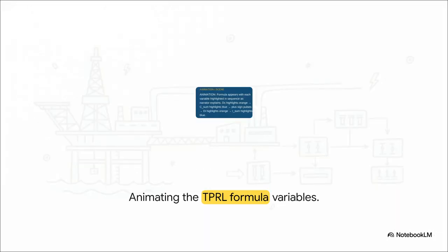It is so cool to watch how this formula logically pieces together. TPRL equals the diversity factor of continuous loads, which is our D, multiplied by the sum of continuous loads. Then you add the diversity factor of intermittent loads, DI, multiplied by the sum of intermittent loads. But notice what is completely missing here. Standby loads. Yep, because under normal, steady-state running conditions, standby loads are entirely de-energized.